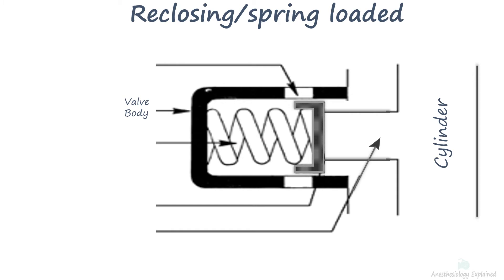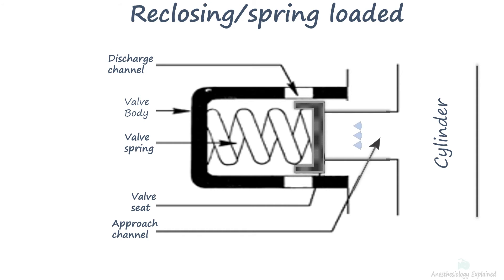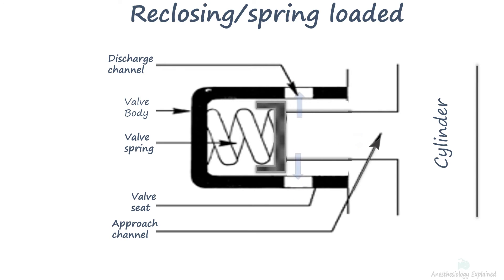At normal operational pressure, the spring within the pressure relief valve exerts firm pressure that forces the seat against the approach channel, effectively closing off the discharge channel. However, when the pressure within the cylinder begins to rise — often due to high temperatures or overfilling — the flow of high-pressure gas exerts force against the seat, compressing the spring and causing the seat to move away from the approach channel. This opens the discharge channel, enabling excess gas to vent safely into the atmosphere. Once pressure is reduced to a safe level, the spring's restorative force pushes the seat back, firmly closing the approach channel once more.